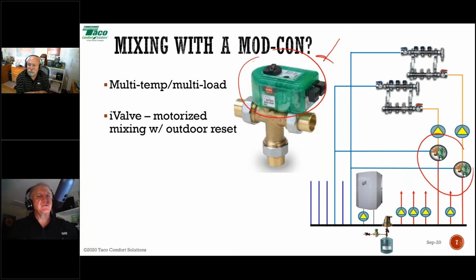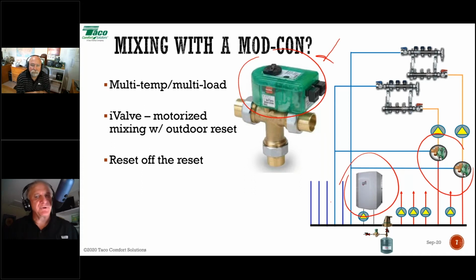What we're doing here, folks, is we're resetting off of the reset. So think about that for a minute. This boiler absolutely loves low return water temperatures. So when we reset off of the reset, whenever either one of these radiants are running, we're going to be sending even lower water temperatures back to the boiler than the boiler itself would have for the high temperature stuff. So these low water temperatures are going back to the boiler, forcing it to condense more and more. And as it warms up and the water temperatures get lower, man, we really start to kick that thing's butt with low return water temperatures, and it'll reward us with extra efficiency.